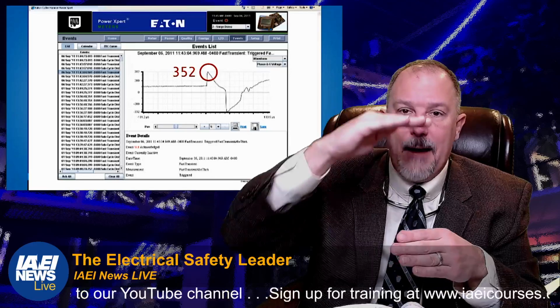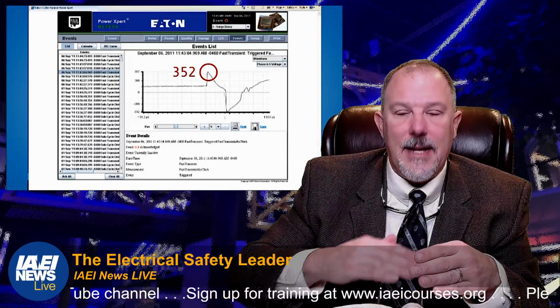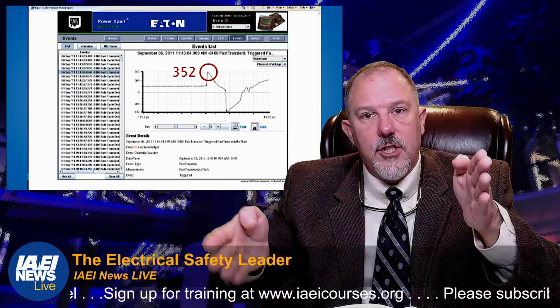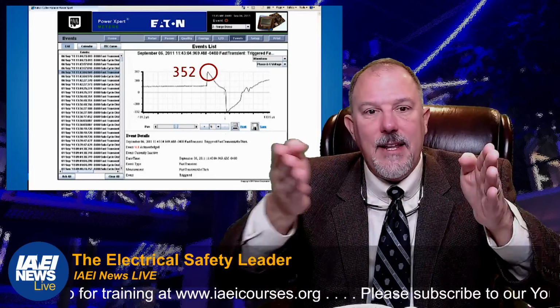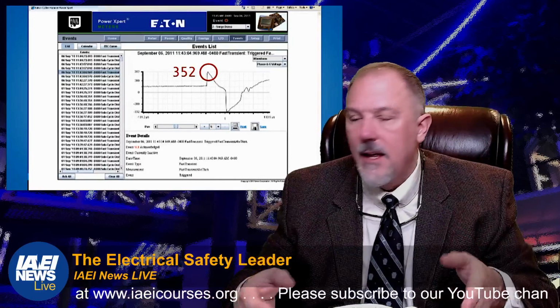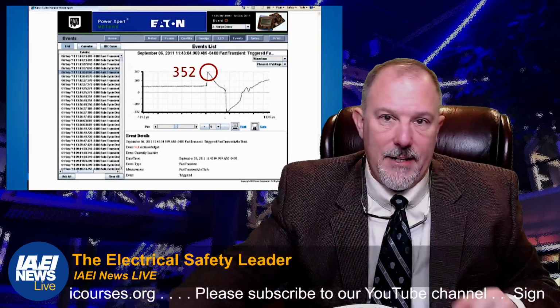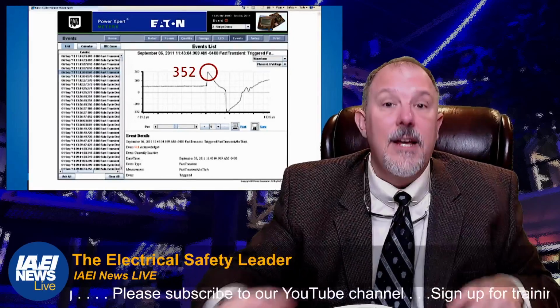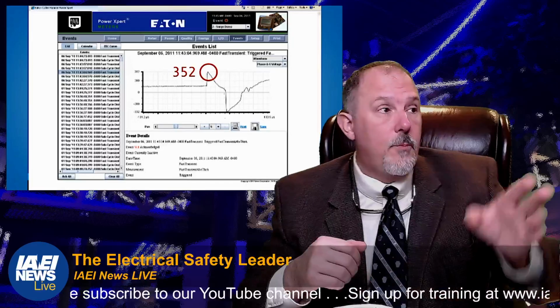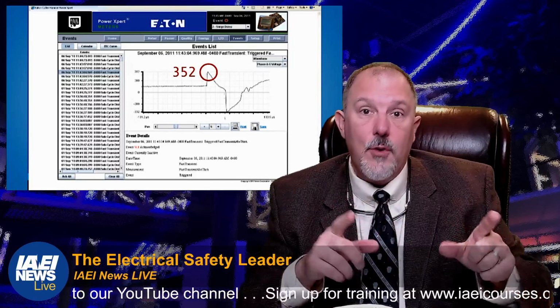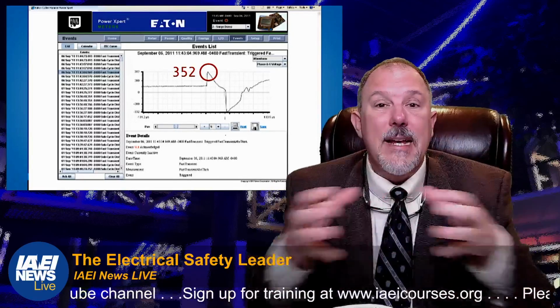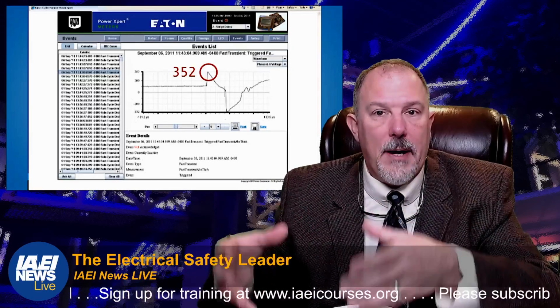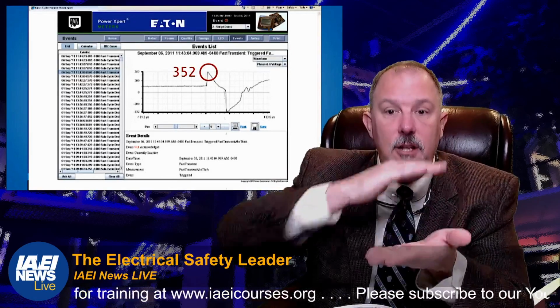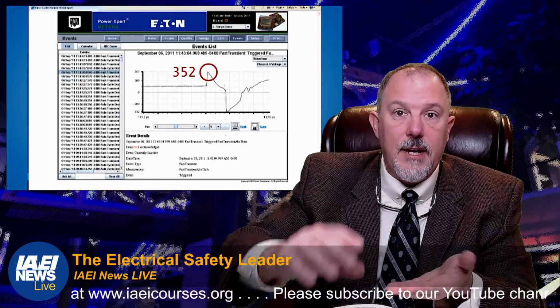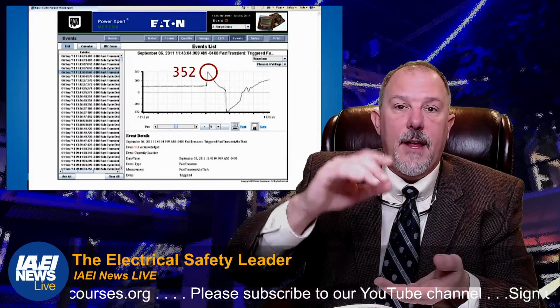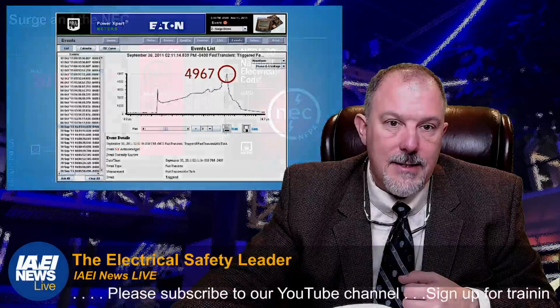Surge protection happens in layers. That's why we layer the surge protection, to keep knocking that voltage down to something that the electronic equipment can manage. That's what we're doing with a surge protective device, and that's why we layer the protection. You just don't put it in one spot and forget it. No, you have it at the service, and then you place it in other locations in your power distribution system, because you're continuously knocking down the voltage. You're getting it into a manageable chunk, and then you are slowly knocking it down.